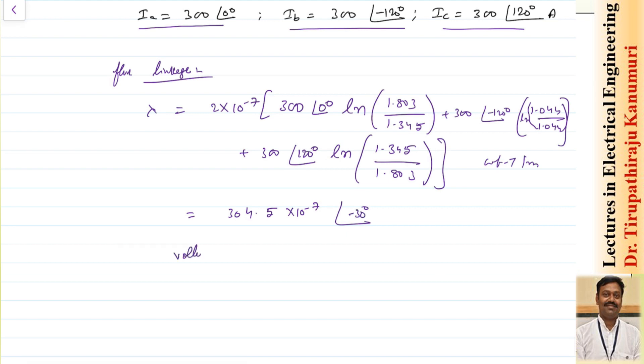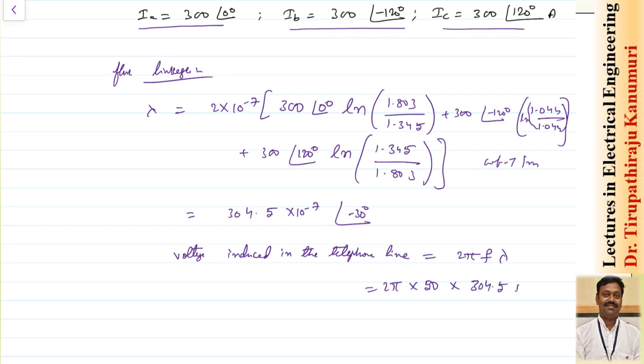The voltage induced in the telephone line is 2πf times lambda. This equals 2π × 50 × 304.5×10⁻⁷, which gives 9.57×10⁻³ volts per meter. So per unit length you are getting 9.57×10⁻³ volts per meter induced in the telephone line.